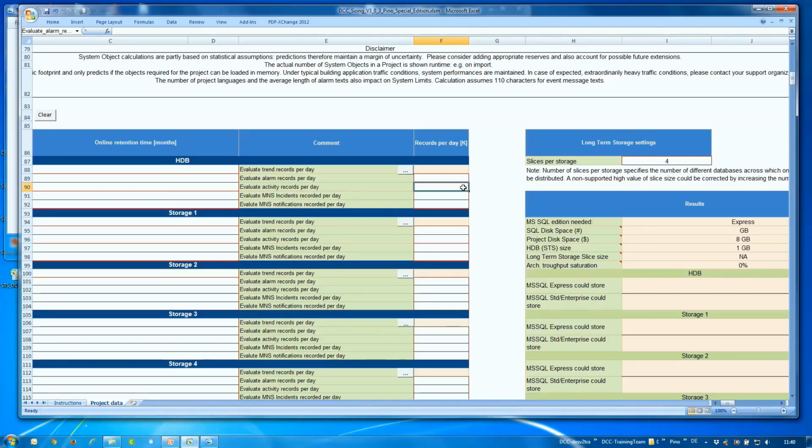From the fire detection system itself, we do not expect any quite huge amount of activities because basically it is in quiet state, just in the lab. So we can just calculate about the doors. So what is an activity? Access, open the door and close the door. Where we have 500 doors, it will be opened 10 times a day, so 5,000 activities.